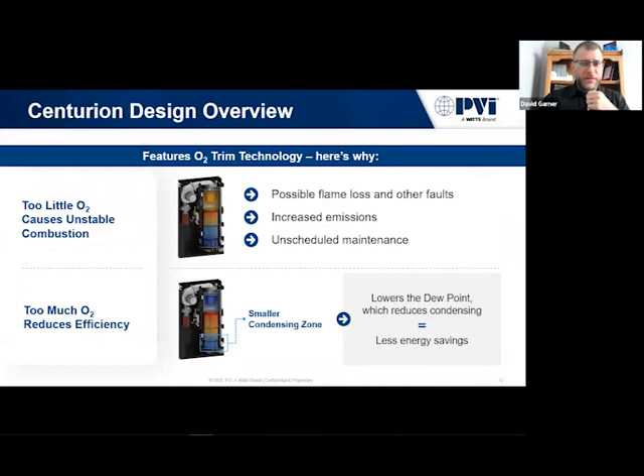For the O2 itself, it's something I think that's typically overlooked: you have problems if you have too little O2. It's an indicator that maybe we're not burning all the gas in the system. There could be unburnt gas going out there, increased emissions. If you have too much O2 during the process of combustion, it actually affects your efficiency.